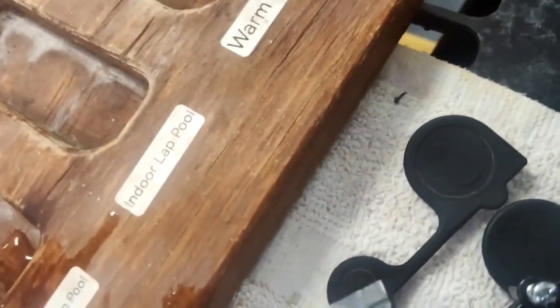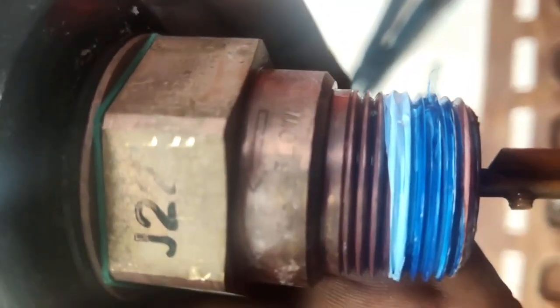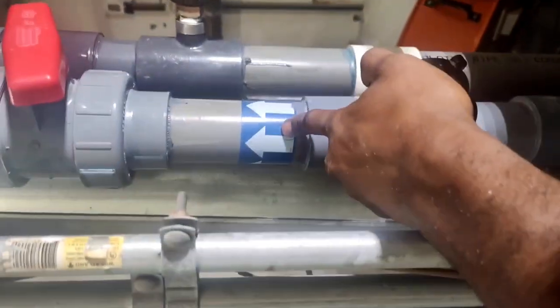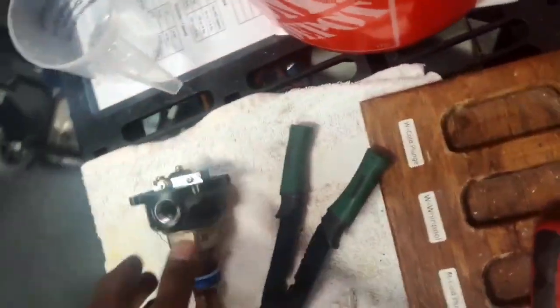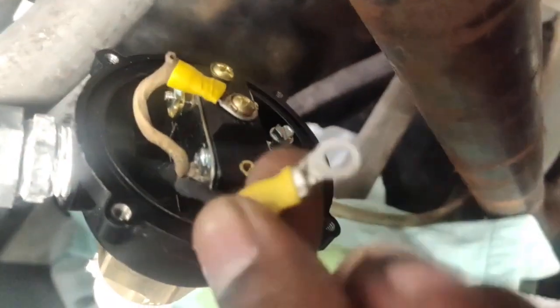And you see on my tools there that they even got this stuff color coordinated at this point. When you crimp that thing down, it'll tell you exactly which crimp to use. The most important thing though is the flow, and the arrow of the flow on the flow switch is facing the direction that the water is going. The other important thing is the length of the paddle. If the length of the paddle is not correct, it will not perform correctly. So I tend to use the same paddle that was from the old flow switch and not use the new flow switch's paddles, because the paddles I got weren't the same size. So I used the same size.